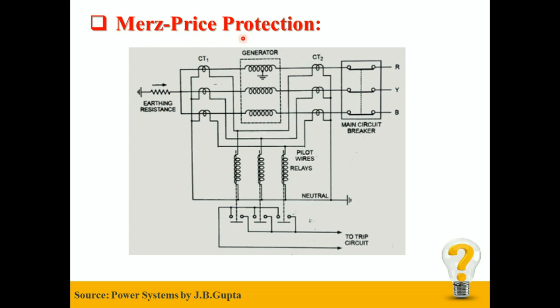Merz-Price Protection: The schematic arrangement of the differential protection scheme of a three-phase generator is shown in the figure. There are two identical sets of CTs; each set is mounted on either side of the stator phase winding of the generator. The secondaries of the CT sets are connected in star, and their ends are connected through the pilot wires. The relays are connected across the equipotential points of the pilot wires, as you can see in the figure.